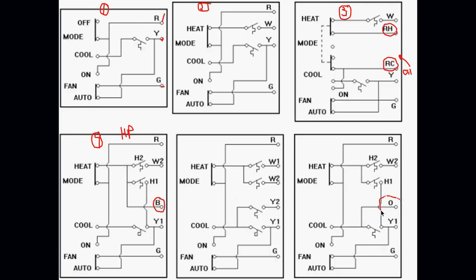Like this one over on, if you look all the way over on the right and see my number six. Yeah, I've seen O as the reversing valve. I just never saw it as B before. Yeah, B is the old style. They don't see it anymore. I don't want to get ahead of myself on here, but B was more heavily used in the southern climates where cooling was the default and we energized the reversing valve for heat. O is more standard now. And O basically says when the system starts, it's in heating mode, and I energize the reversing valve for cooling.